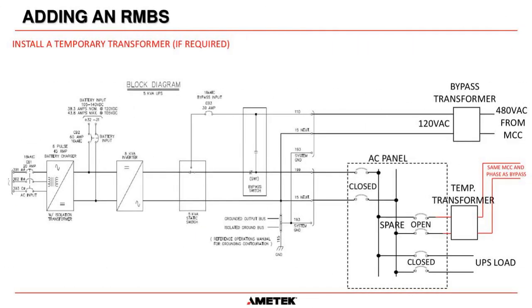And then what we need to do is install a temporary transformer. Now I say if required, because on the majority of systems, the MCC is feeding 480 volts single phase into a bypass transformer, and that gets stepped down to 120. In very rare occasions, this transformer isn't needed because they're taking 120 volts directly from an MCC, if that's possible. But what we see most of the time is there is a bypass transformer. And what we need to do is we need to make sure that the power that we are supplying into this spare breaker here is exactly the same as this voltage here. Now, with a single phase transformer, there is no phase shift.